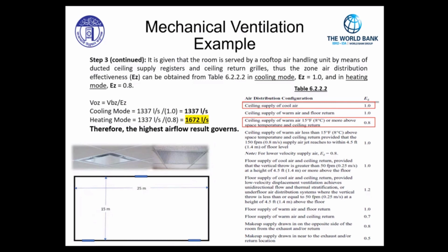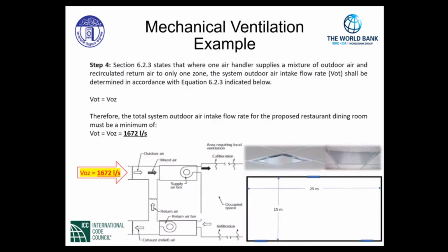1,337 liters per second. However, in heating mode, we take the heating mode value, and as seen here in the denominator, it is less than 1, so that's going to drive up the end result to 1,672 liters per second. This is the value that we need to use for our outdoor airflow rate in this part of the process. Step 4.